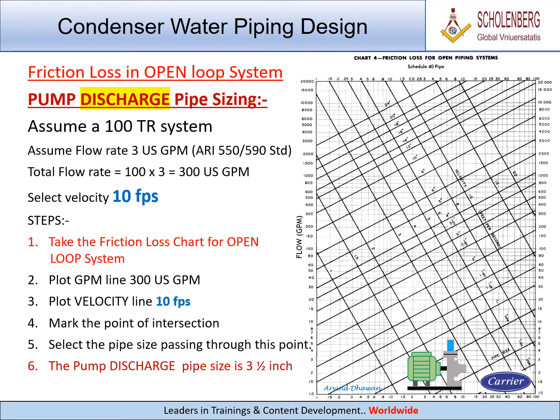Pump discharge pipe sizing. Assume a 100 TR system. Assume flow rate 3 USGPM per ARI 550-590 standard. Total flow rate equals 100 multiplied by 3 equals 300 USGPM. Select velocity 10 FPS.